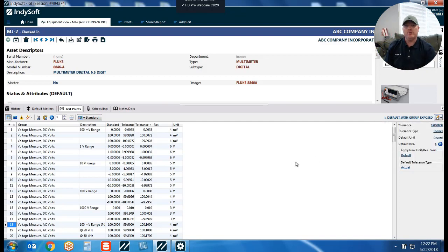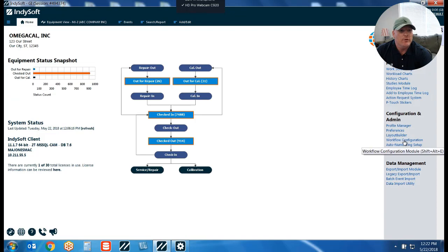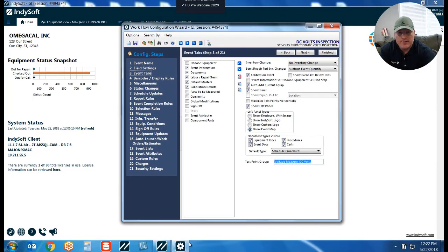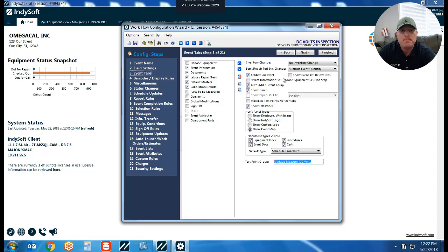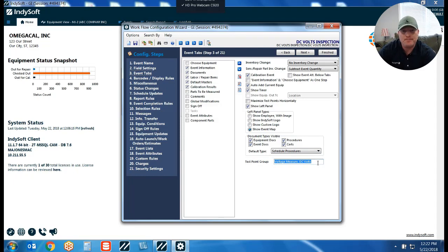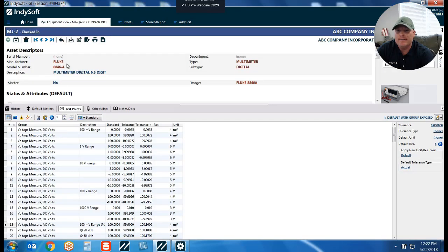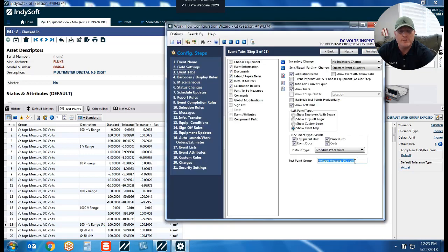So first we make the group column visible. The second setup step is to open up Workflow Configuration. Inside workflow config, in the event tabs configuration step, you'll see at the bottom where you can indicate which test point group you want to be visible or utilized based on a particular event. In my event called DC Volts Inspection, I've set it up so my test point group called 'Voltage Measure, DC Volts' actually defaults in. Going back to look at the equipment, there's the test point group 'Voltage Measure, DC Volts' — that's exactly what's going to default and pull in.